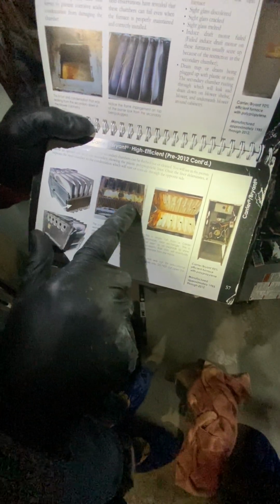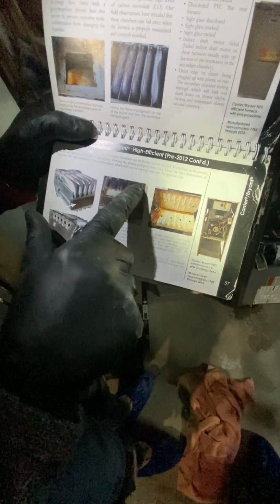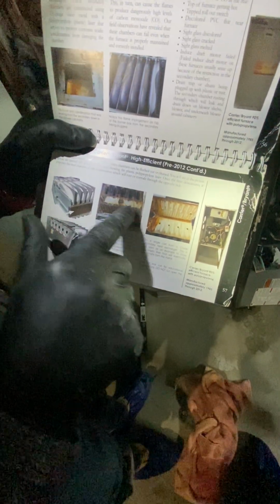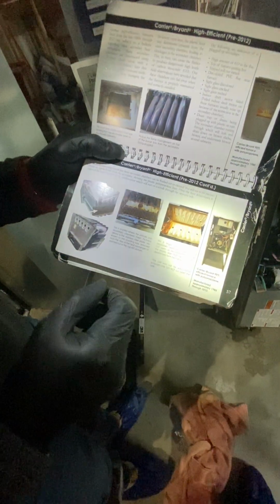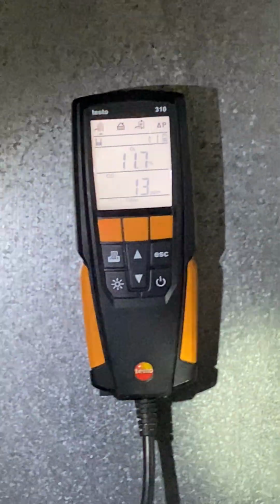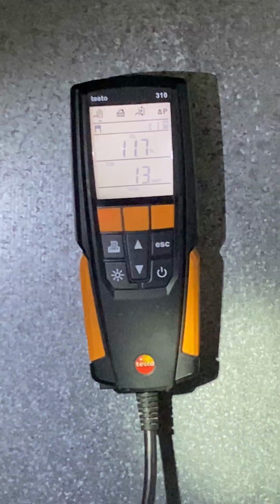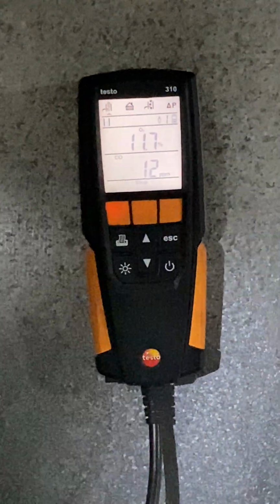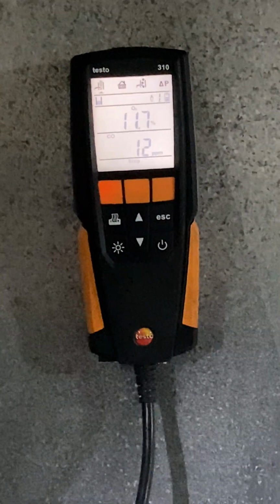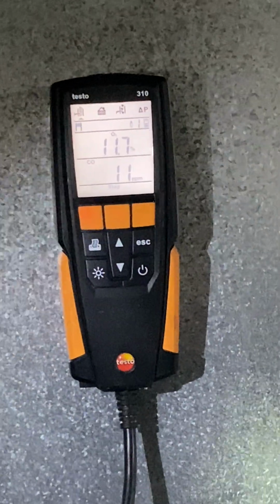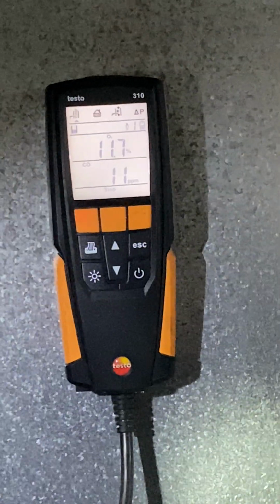So it corrodes the inside of it, and when it goes from the primary to the secondary, these things are completely clogged. So the flue gas gets stuck in there, causing a high CO. That's what beat up heat exchangers look like, and that's not when people install furnaces and they don't have a pitch on them. But you got a low ppm, meaning that's good. There's no high CO. That's the telltale sign, meaning all the flue gas is flowing through the system and to the outside.